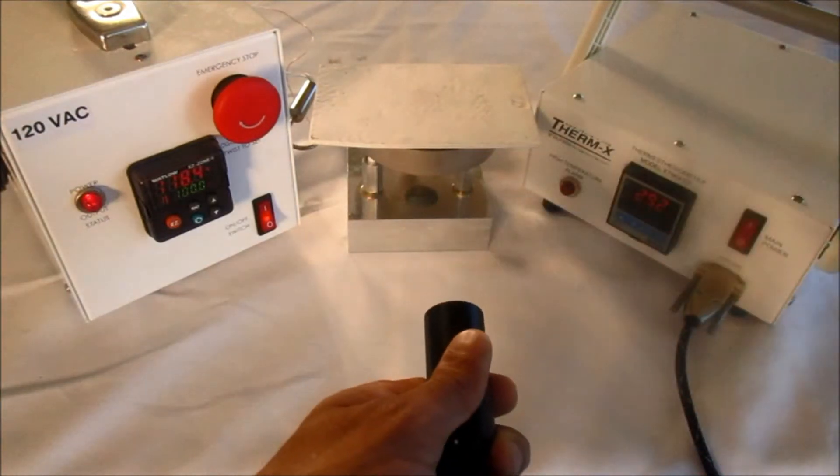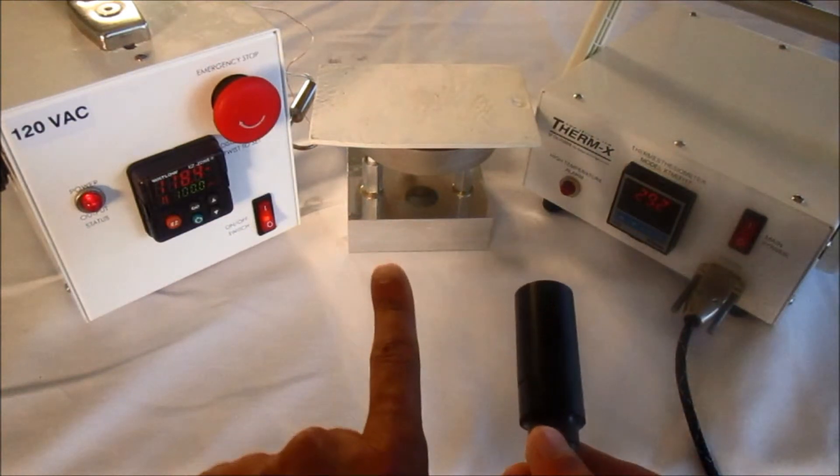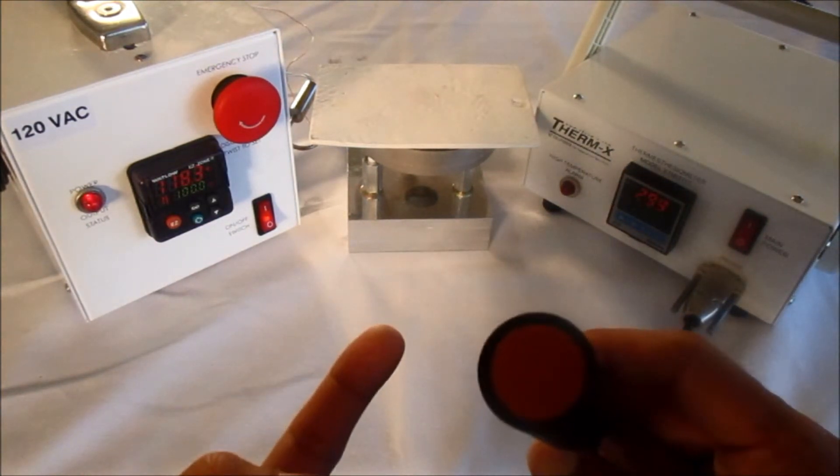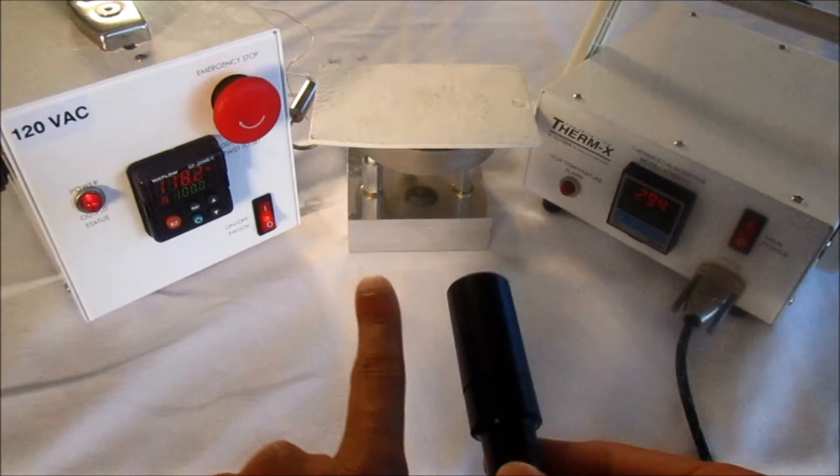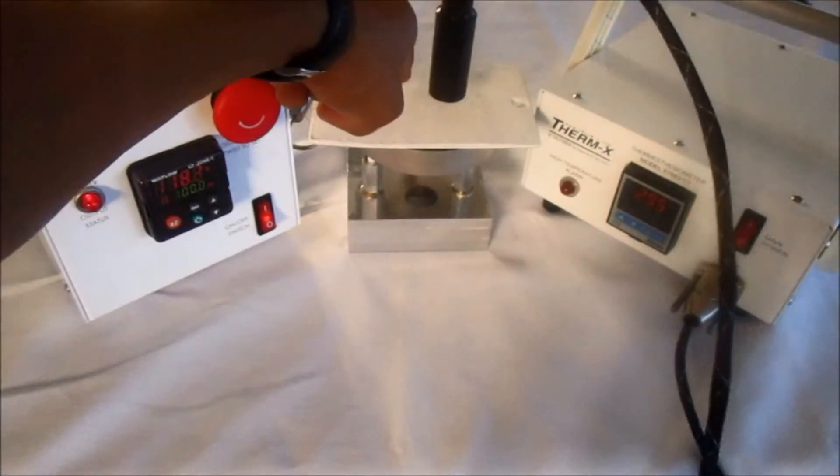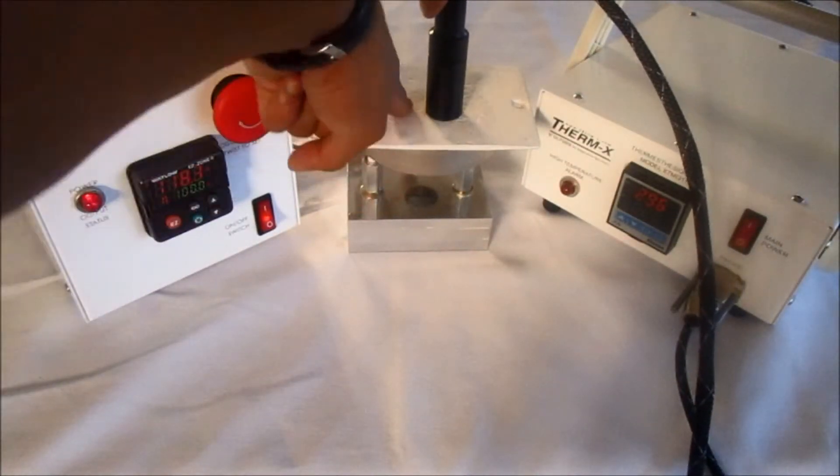One demonstration uses an aluminum sheet coated with ceramic insulation. With our thermesthesiometer, by quickly placing the probe on the ceramic surface, you are able to find an accurate temperature that is safe for human touch.